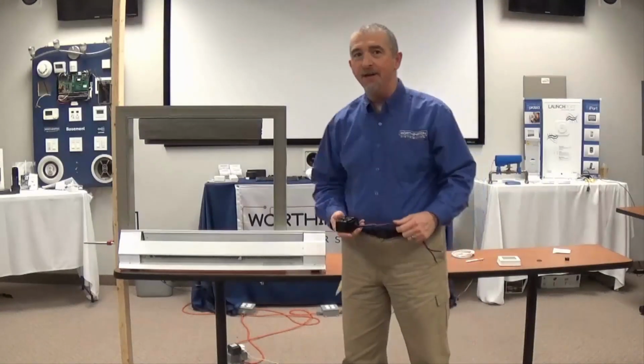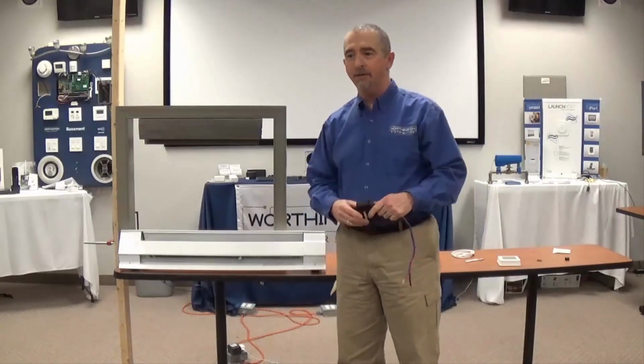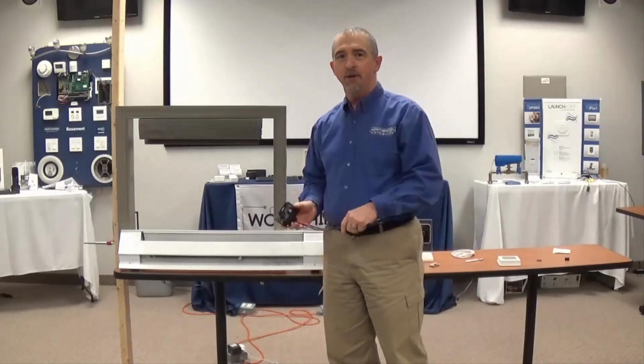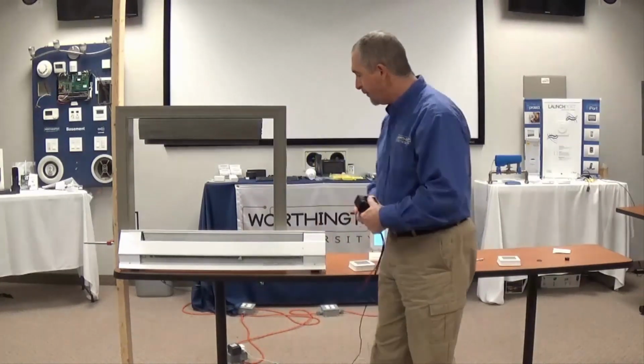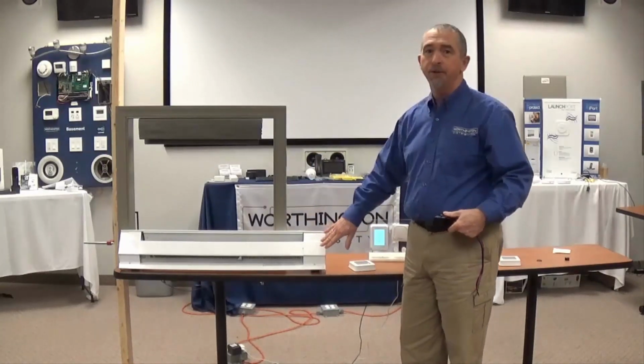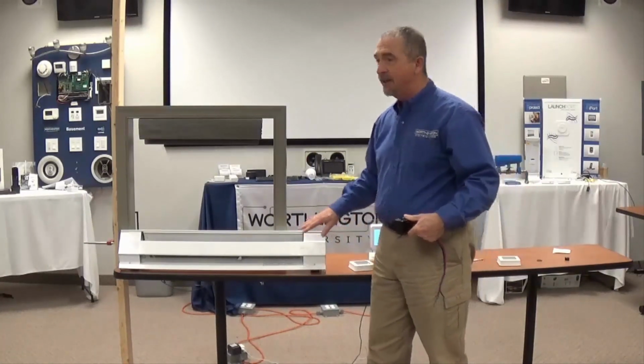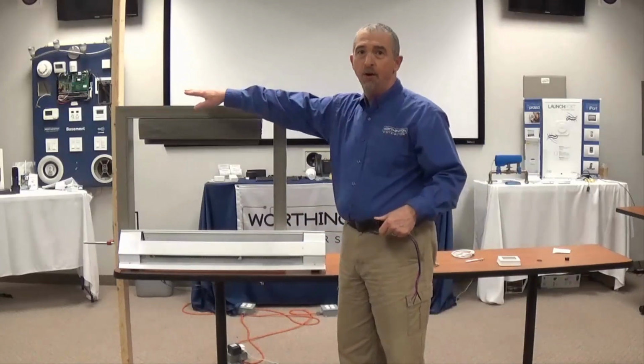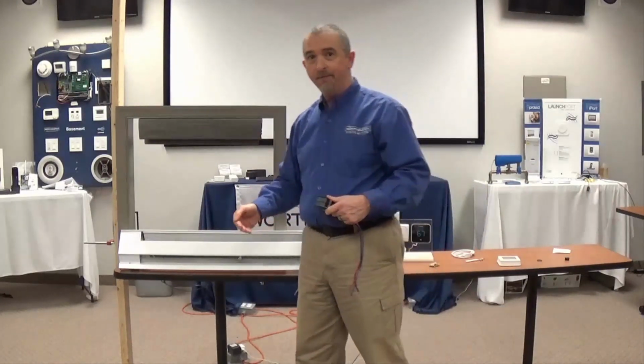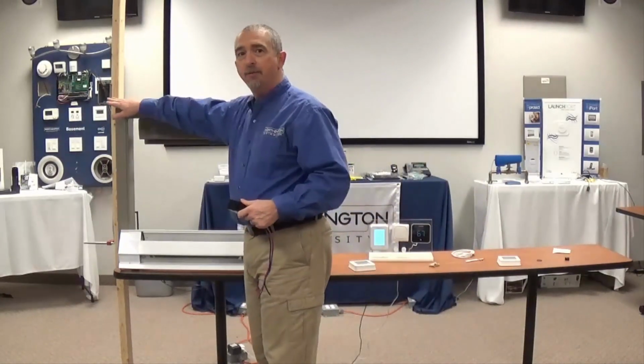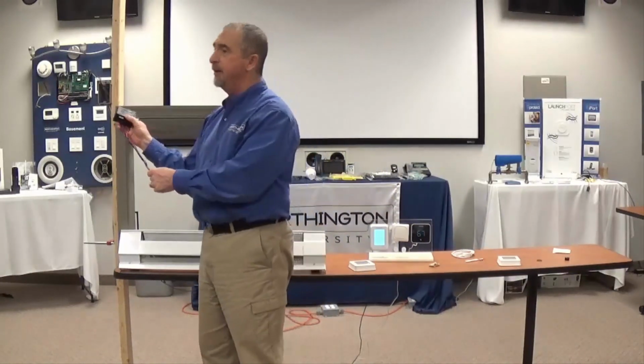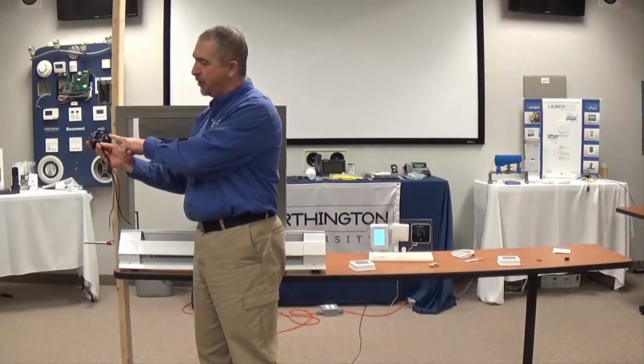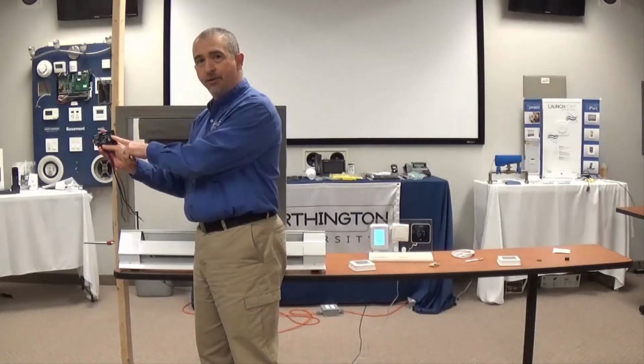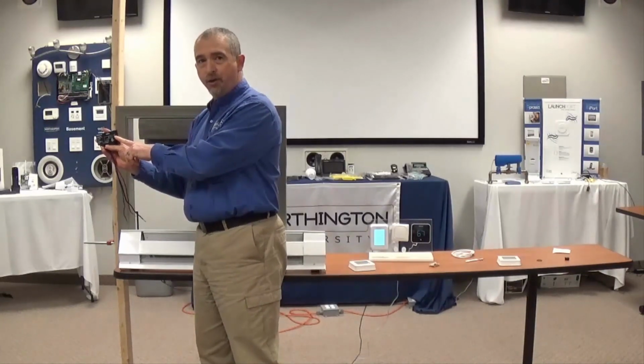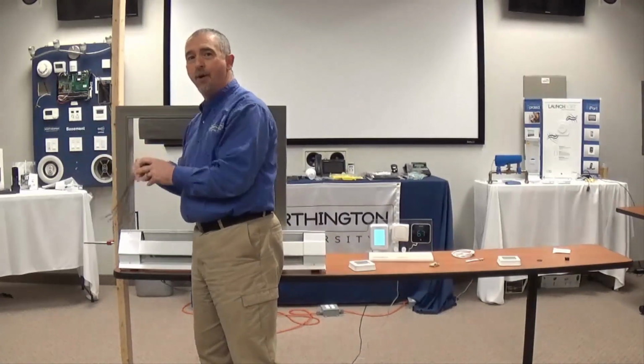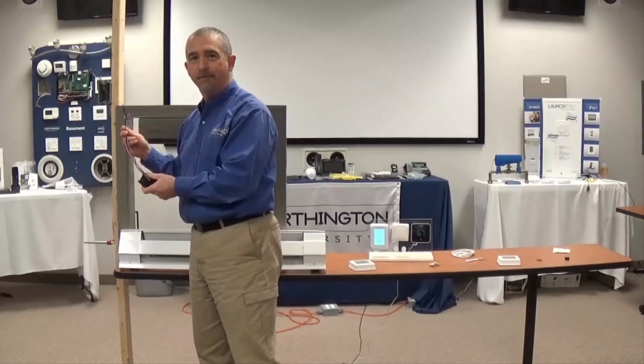Okay, I'm back, and now I've got another example of using this module with a 220 volt baseboard heater. In this example, there was no built-in thermostat, so we need to tie into a thermostat that's already on the wall. We turned off the power, removed the existing thermostat, and we're going to wire this module in, then take small jumpers from the low voltage connections to the low voltage thermostat. So once again, I'm going to wire this up and I'll be back in a moment.